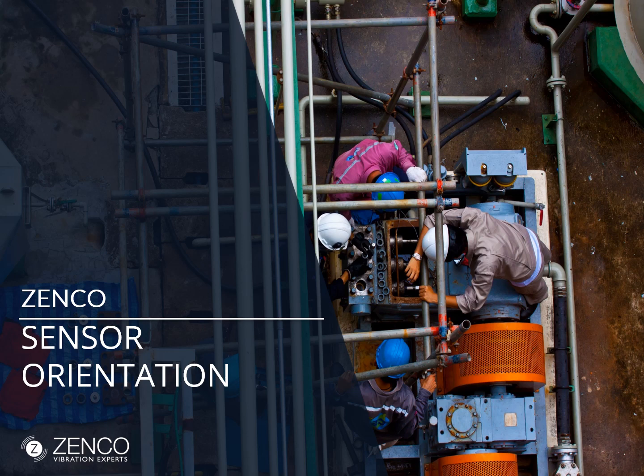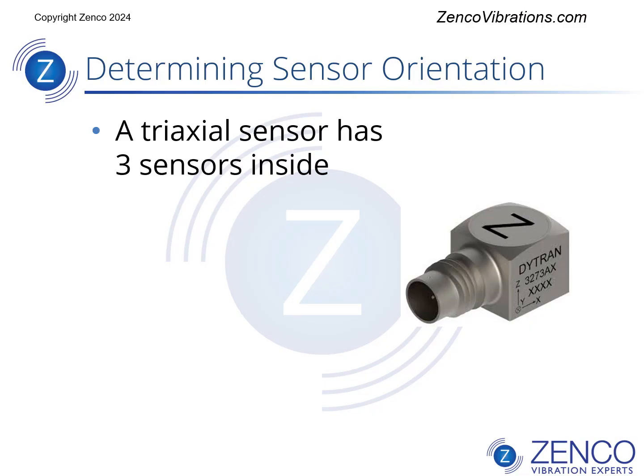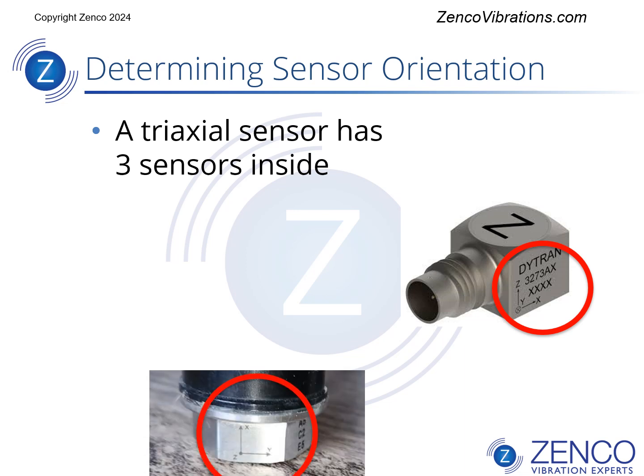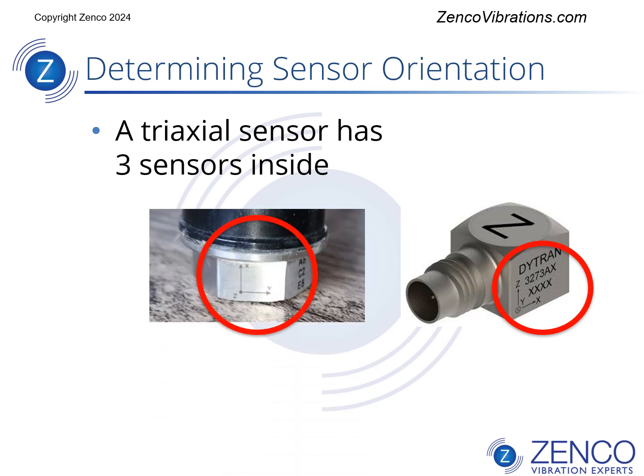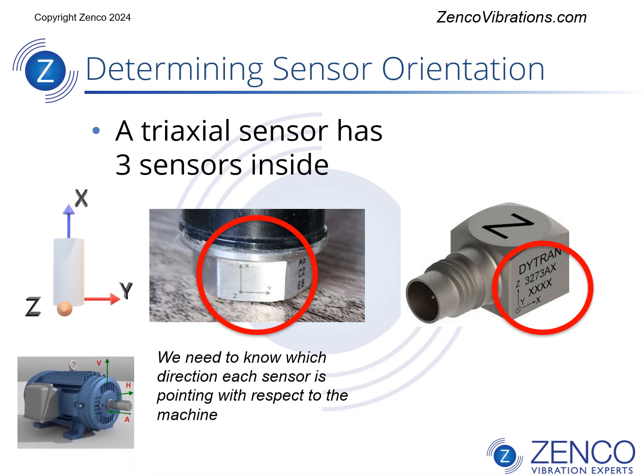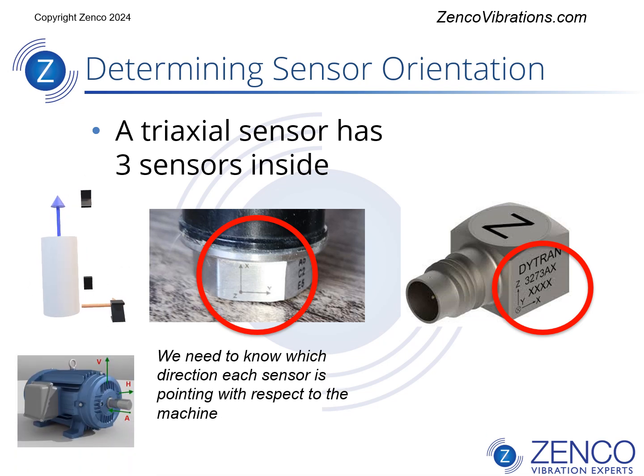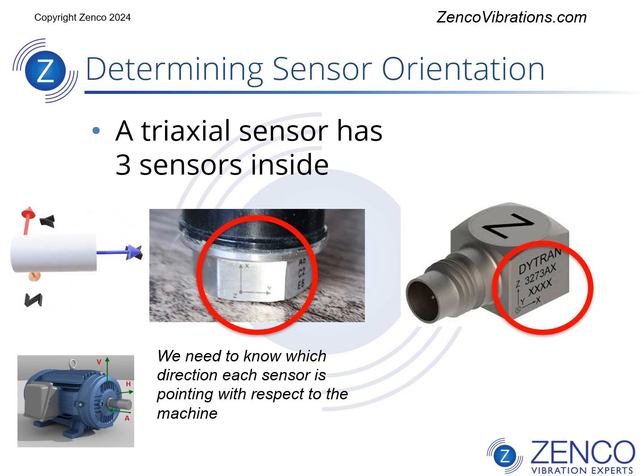This is going to be a short presentation on defining sensor orientations for vibration sensors. This is a tri-axial accelerometer. It has three sensors inside — in this case they are labeled X, Y, and Z. We need to know, relative to our machine, which direction each of these sensors is pointing.